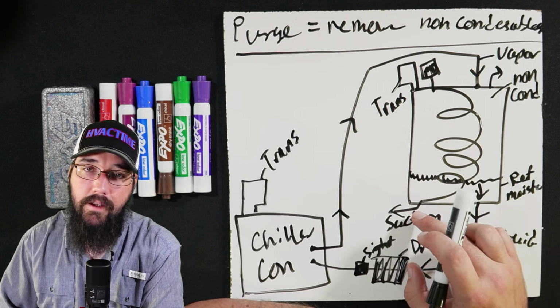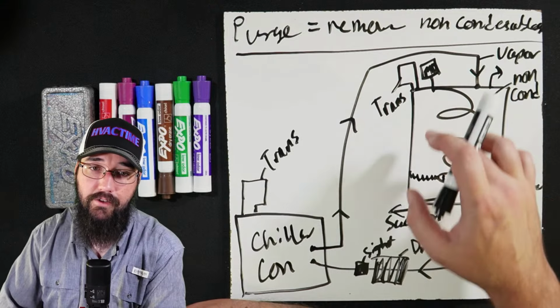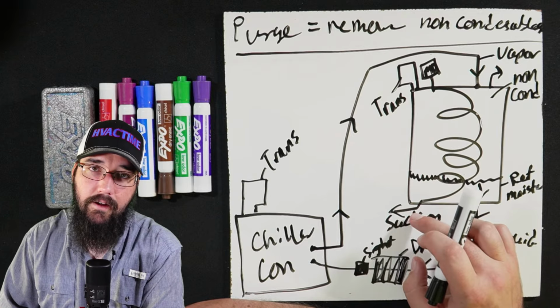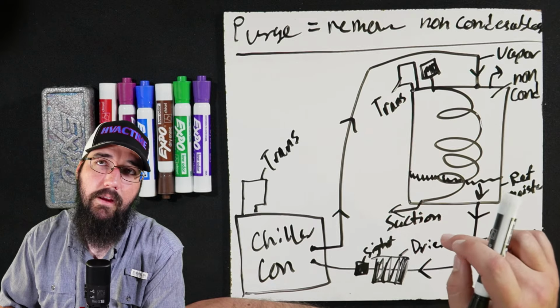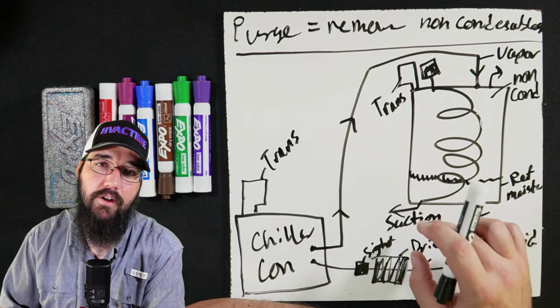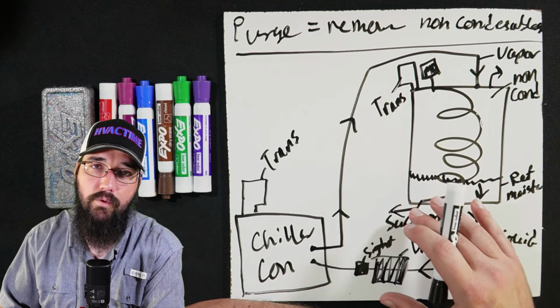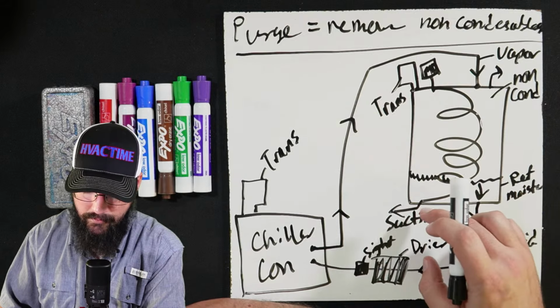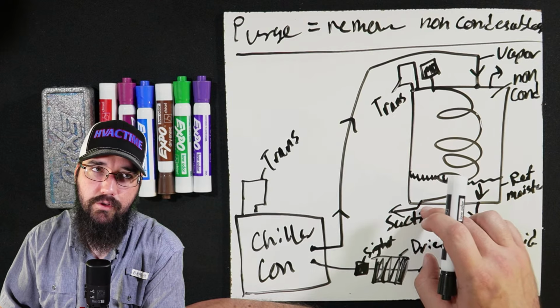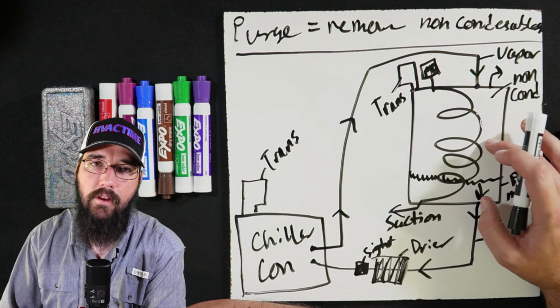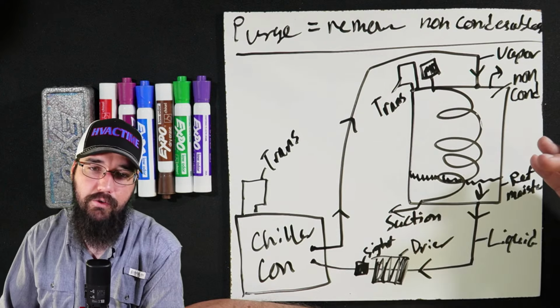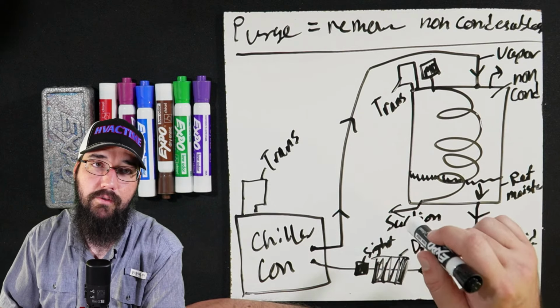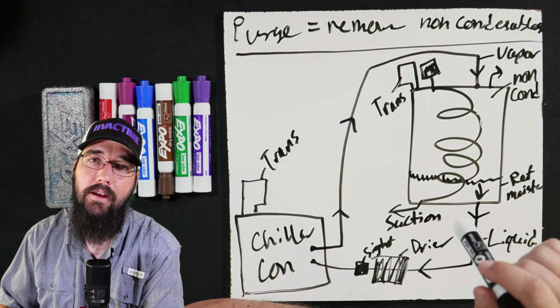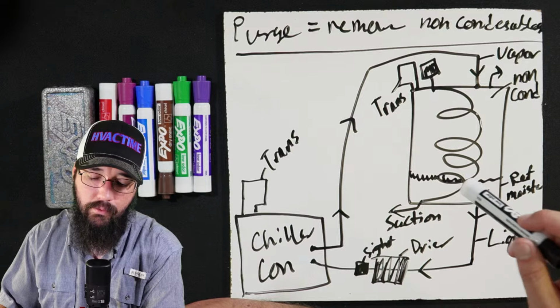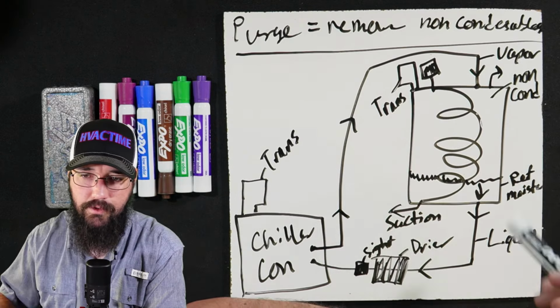suction line temperature. So when this evaporator coil in this chamber needs a pump out, when the superheat, basically the suction line temperature, drops below a certain threshold, which is like 28 degrees, the control system knows, okay, this chamber is full, we need to do a pump out. So that's how Trane is doing it as a contrast: they're monitoring the purge compressor suction temperature. That is what indicates it needs a pump out, whereas York is doing the transducer, just to give a contrast as to how they're going about it.